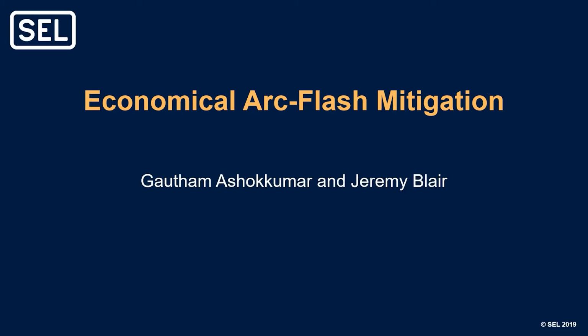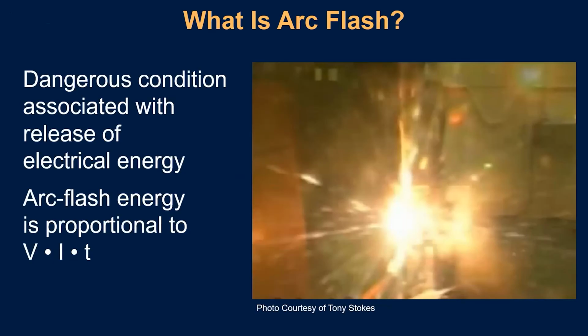So we've all heard of arc flash. We know it's a dangerous condition that can cause enormous damage to both equipment and people. The energy caused by the formation of that arc is proportional to the electrical energy that's available, which in turn is the product of the voltage times the current times the duration that this arc persists.